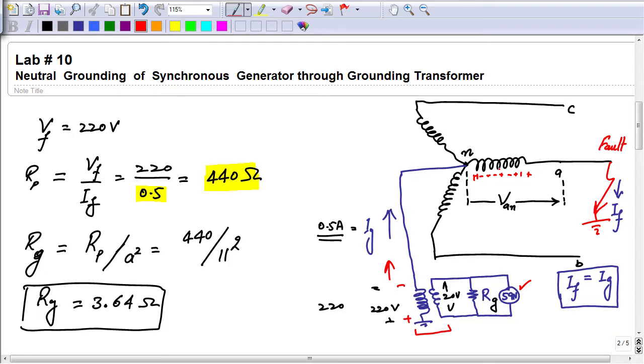So if a fault occurs, let's say exactly at the midpoint of the generator winding, which gets short circuited with the ground, then between this neutral point and the midpoint, the fault point, the voltage will be VAN over 2, half of the rated voltage of that winding. For example, in this particular example we get only 110 volt across the primary of this transformer. This 110 will give us 10 volt on the secondary side, and the relay would be set to a very low value, maybe 1 volt or 2 volt, which can easily detect this 10 volt and respond to operate the circuit breaker or activate an alarm. This is how our voltage relay can sense the fault.